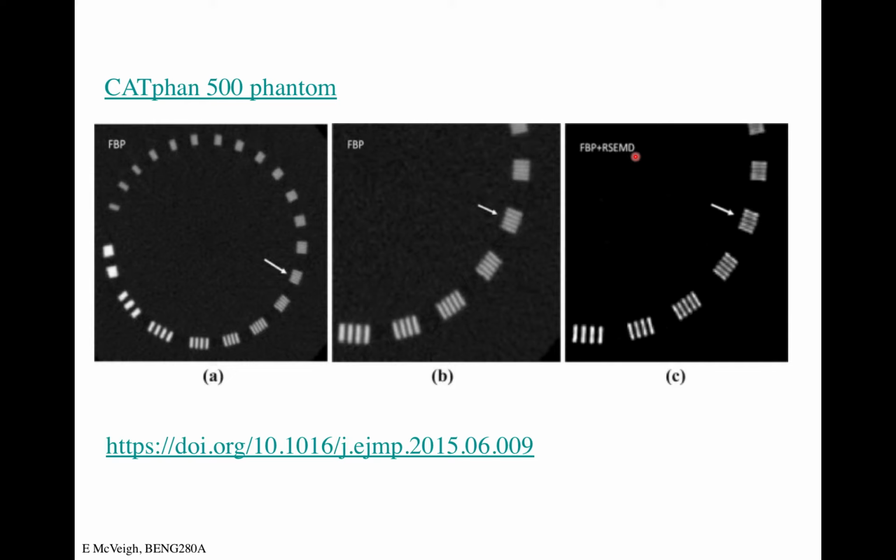Oh, I see. So the question, I think, is what is the limit on the dimensions of the scanner with respect to the source to detector distance? And sort of, if you can optimize it by minimizing that distance, where is the cutoff for a manufacturer to say, there's no point getting any closer? Right. Well, a lot of that is partially set by the mechanics of you got to rotate this darn thing and put a patient in the middle of it, right?